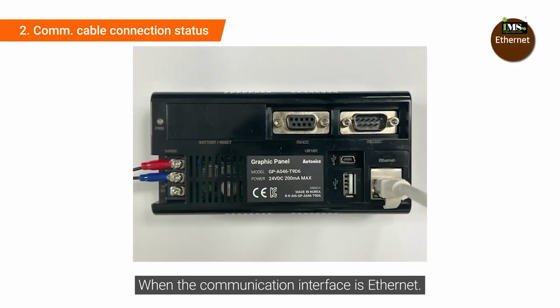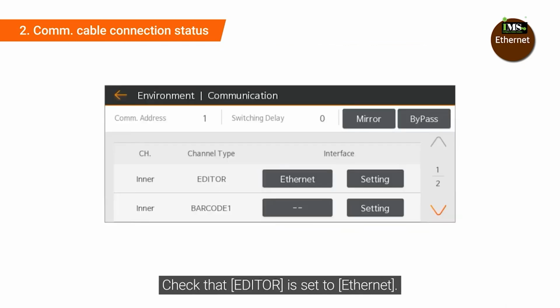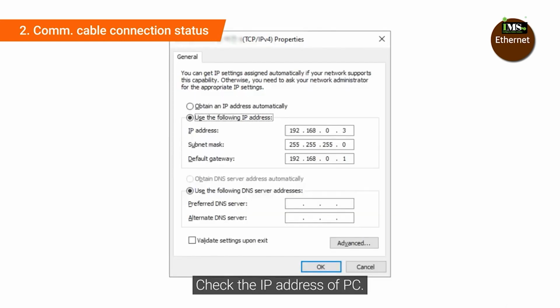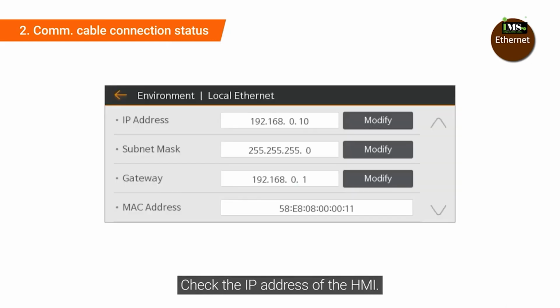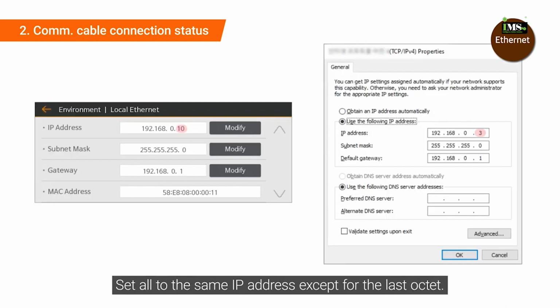When the communication interface is Ethernet, check that the editor is set to Ethernet. Check the IP address of the PC. Check the IP address of the HMI. Set all to the same IP address except for the last octet.